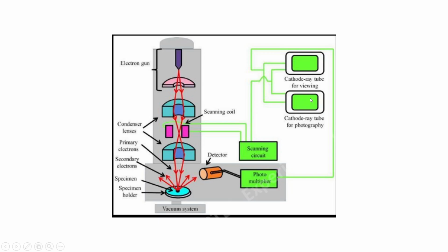If something has depth, it will show in those black and white images; you can see the depth slightly. So this is why we need a conductive material. If you have gold coating, it will make the samples conductive, and this secondary electron emission can happen easily, and these secondary electrons will be captured by the detector to see the image.